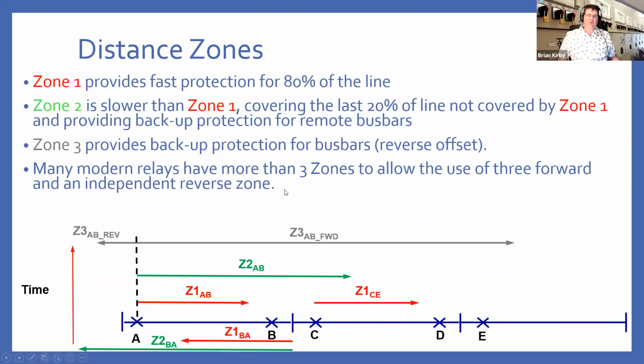So distance itself will normally operate multiple zones. You will have zone 1. You see here, this section, you will have distance in both directions with an overlap, and they are the high-speed tripping for your in-zone faults. So they should operate for any fault in that zone. Similarly, any fault in this zone will have similar arrangements, and that should operate first.